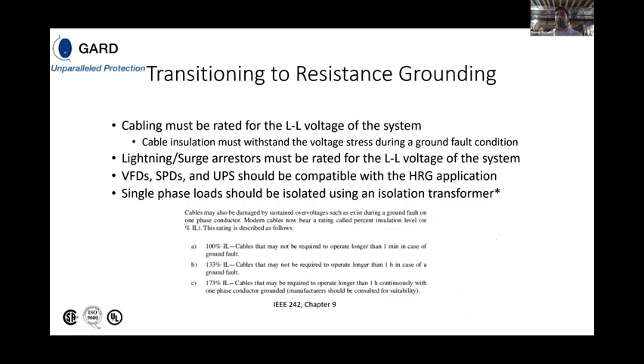Now, when we're considering a resistance grounded system, we have to ensure that the cabling is rated for the line-to-line voltage of the system. As seen in the previous slide, we had a phase to ground fault that caused elevation on the unfaulted phases. So we need to make sure that our cabling, our lightning arrestors, and our surge arrestors are also rated for the line-to-line voltage, such that it can handle that voltage stress during the first phase to ground fault.